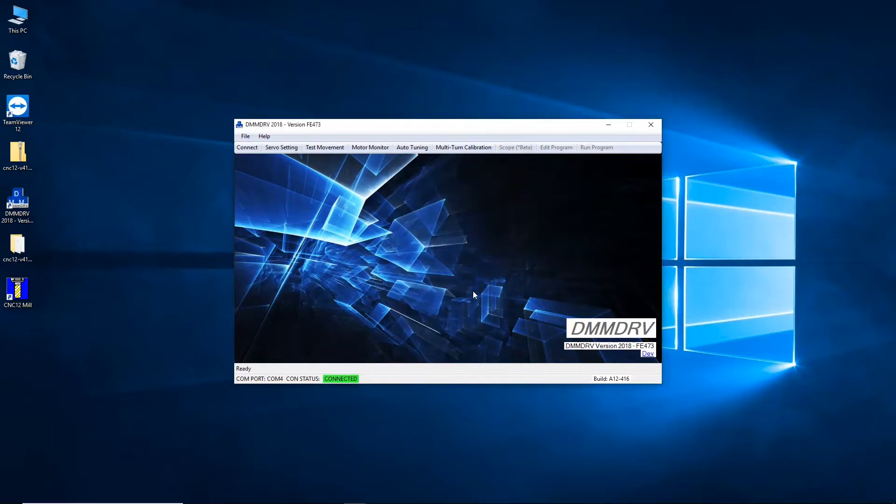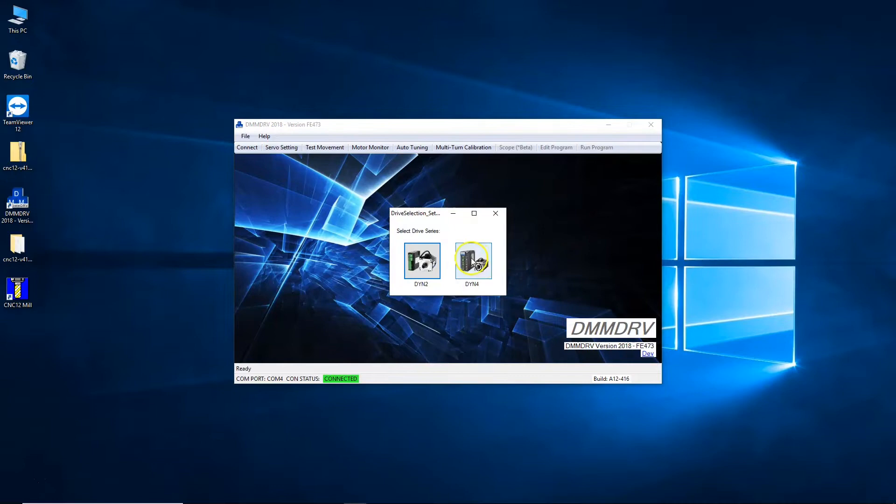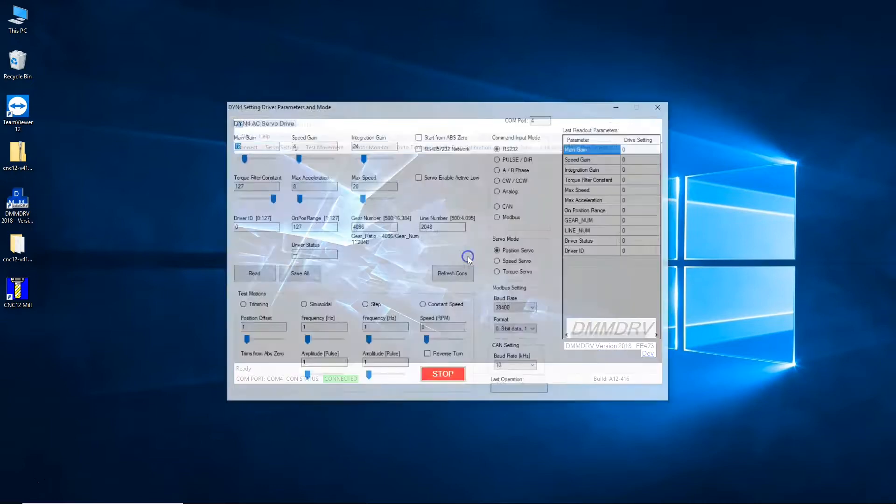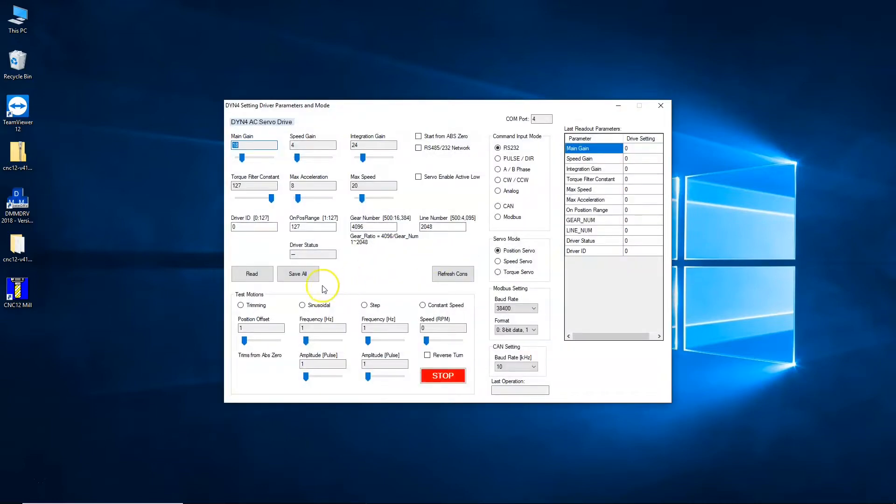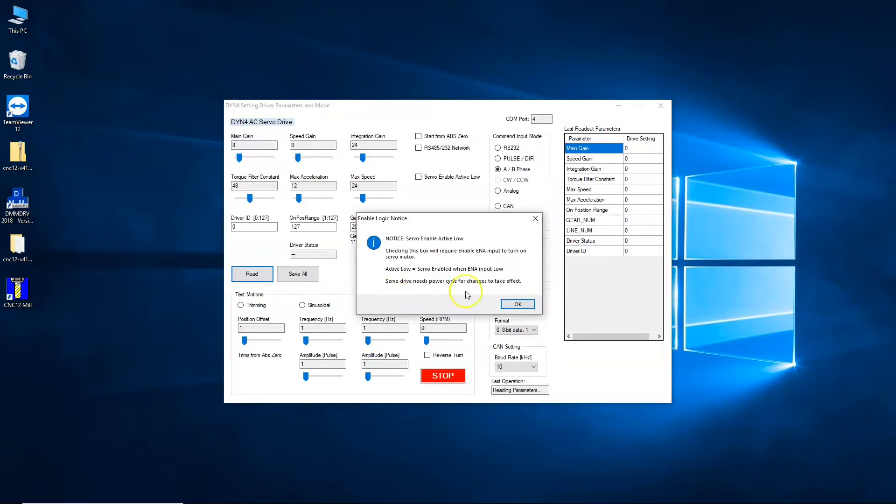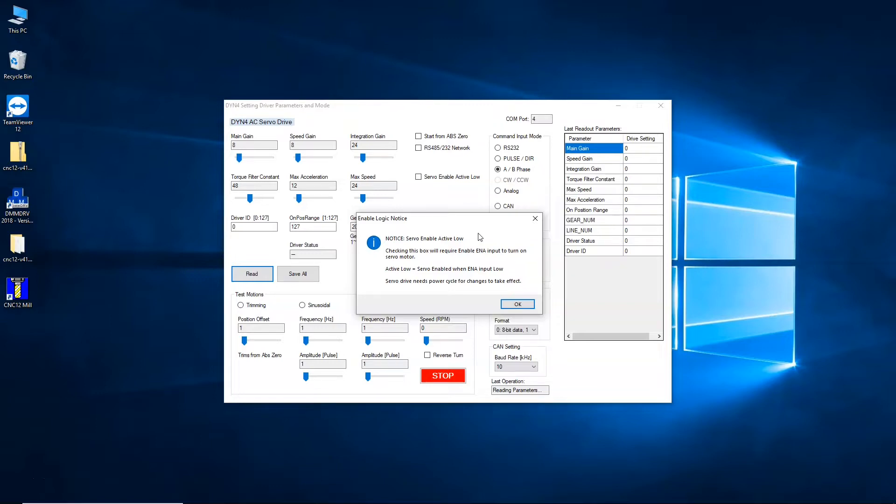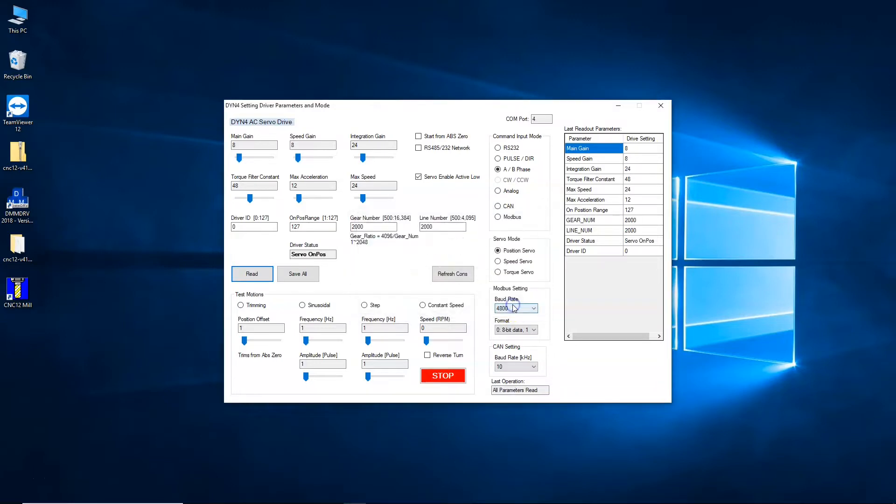Com port successful. We're connected. We're going to go into servo setting, choose DYN4, and read from this drive so you can take a look and see the basic settings. Notice servo enable active low - checking this box will require the enable input to turn on the servo motor. This box needs to be checked.